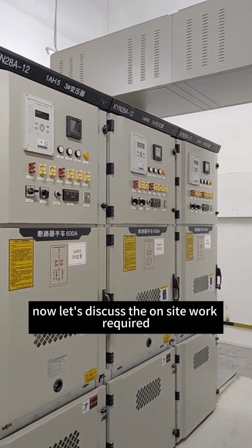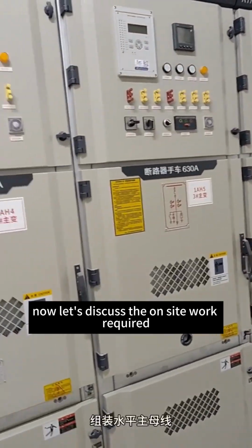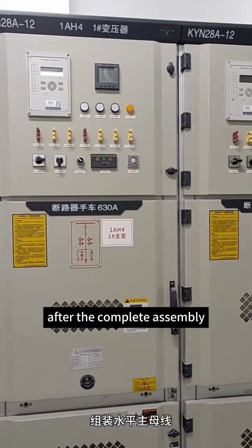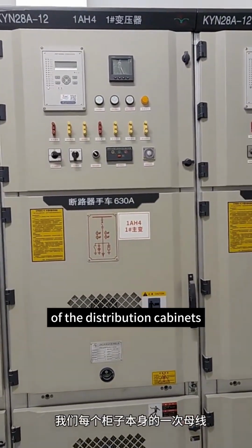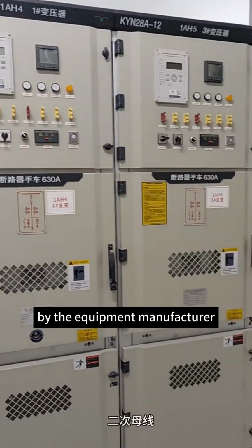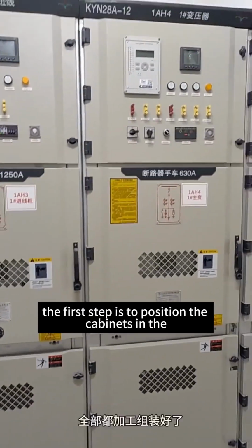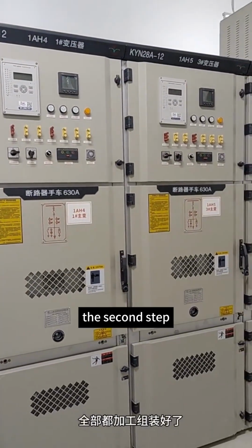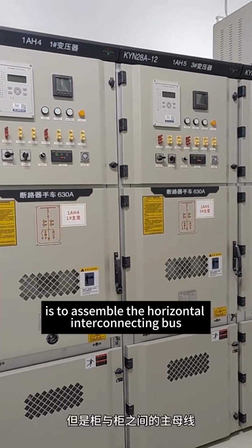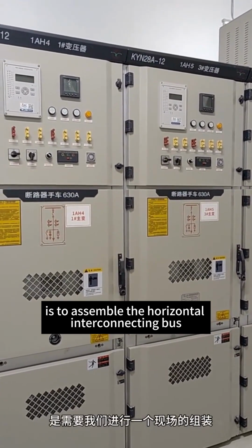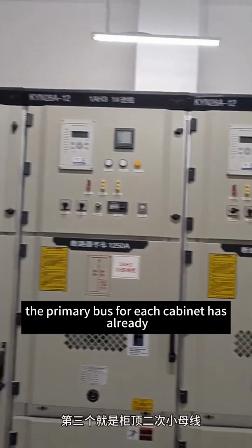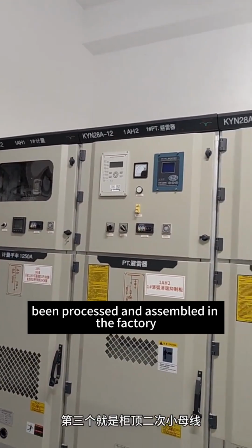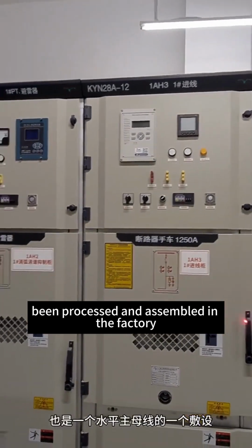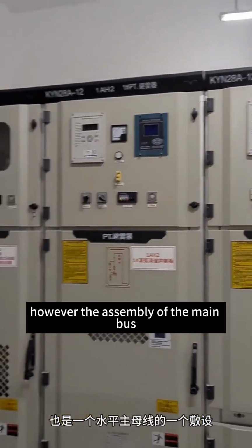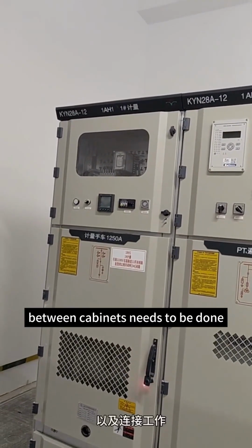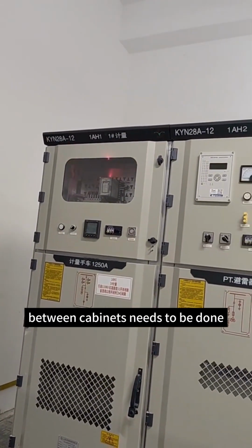Now let's discuss the on-site work required after the complete assembly of the distribution cabinets by the equipment manufacturer. The first step is to position the cabinets in the designated arrangement order. The second step is to assemble the horizontal interconnecting bus. The primary bus for each cabinet has already been processed and assembled in the factory. However, the assembly of the main bus between cabinets needs to be done on site.